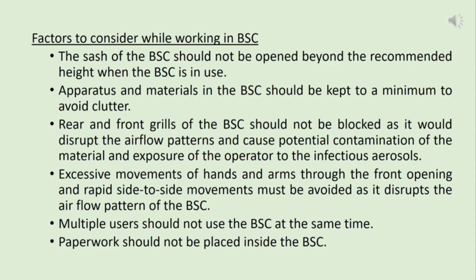Then the materials which you bring into the biosafety cabinet should be kept to a minimum. You should avoid clutter, because if you have too many items in the BSC, it may cause spillages, and you don't have much room to work. And as I said earlier, the front grills and the rear grills should not be blocked with items, because it will disrupt the airflow patterns in the BSC. This can cause contamination of your samples and exposure of the operator to infectious aerosols.